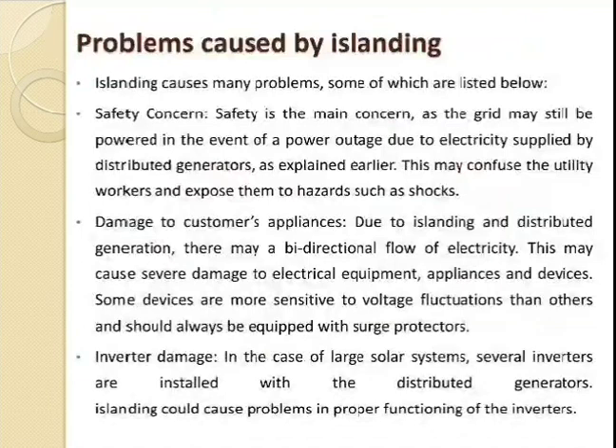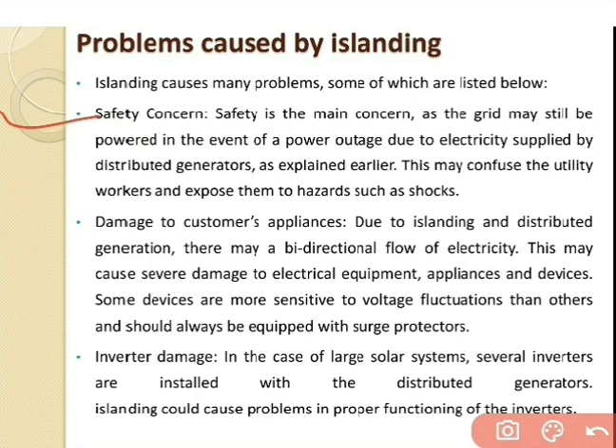Now, problems caused by islanding. There are a number of problems listed below. First is the safety concern. Safety is the main concern, as the grid may still be powered in the event of a power outage due to electricity supply by the distributed generator. This may confuse utility workers and expose them to hazards such as electric shocks. If any unbalancing condition occurs at the load side, a large amount of current flowing in the circuit may cause a shocking condition to workers.